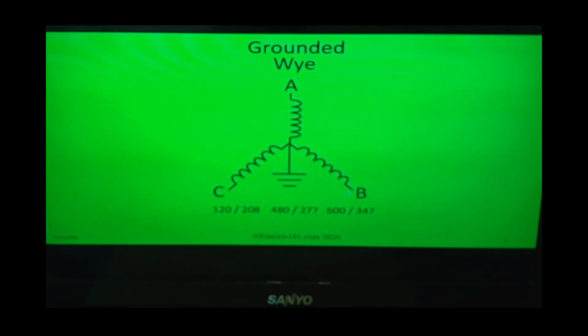Now, also used in the U.S. and becoming more and more popular is 600/347. So 600/347, measuring between A and C, A and B, C and B, it's all going to be 600 volts. And if I measure the neutral, it's going to be 347. There's a lot of use for this type of transformer, especially when you start calculating the cost of copper wire.